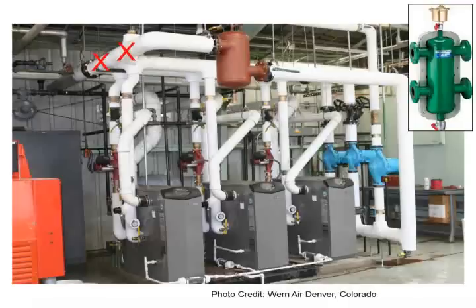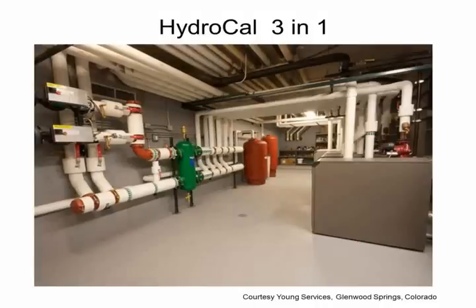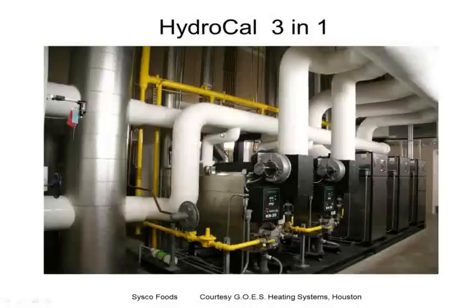Alternatively, using a HydroCal, a 3-in-1 device, could have given the designer an option to, instead of using closely spaced Ts, use the HydroCal and not have the Y strainers, because the dirt separation capabilities of the HydroCal would do that, and the air separation would also be handled by that one device. So here's an example of where it could be applied as an alternative, such as this job up in Colorado where they used the HydroCal as a 3-in-1 device, eliminating those other pieces of equipment.